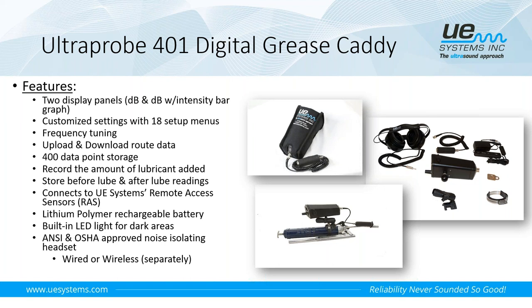We've already talked about the frequency tuning capability. So like I said, it will come set from the factory at 30 kilohertz, which is the optimal frequency for bearing inspection. The only time that you would want to look to adjust that would be on your slower RPM bearings. So again, anything typically below 100 RPM, you may want to adjust that frequency down into the 20 to 25 kilohertz range. That'll give you better results on your slower speed bearings.